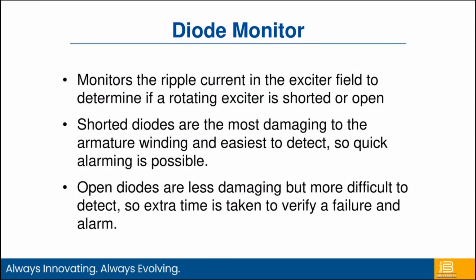Another one of those black boxes that were out in those systems were diode monitors. So brushless exciters have rotating diodes in them to provide the excitation to the field through the exciter. What happens is every time one of those diodes fires, it will produce a ripple current, which is reflected back into the exciter field.